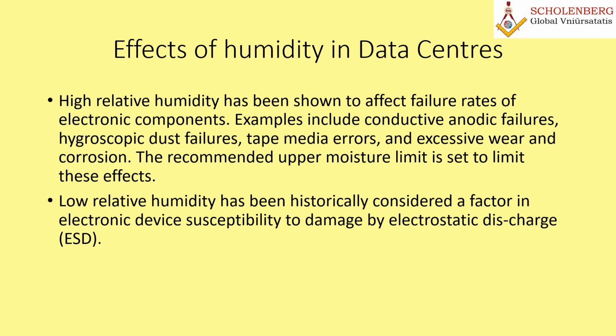Let's discuss the effects of humidity in the data center. This is the most misunderstood topic, my friends. Now we are going to throw some light on it from the ASHRAE point of view. The ASHRAE 2019 Handbook for Applications clearly states the effect of high relative humidity and low humidity, which we are going to talk about now. The effects of improper moisture control on data center operations are twofold. One is high relative humidity, which has been shown to affect the failure rates of electronic equipment. The examples include conductive anodic failures, hygroscopic dust failures, tape media errors, excessive wear and corrosion.